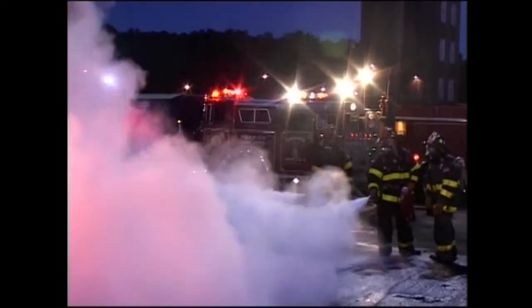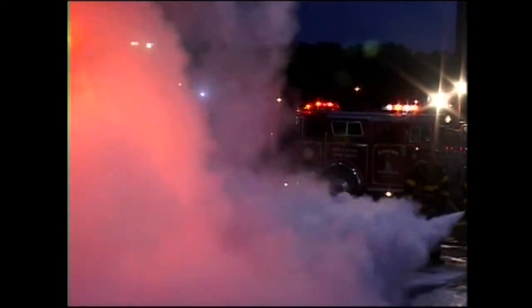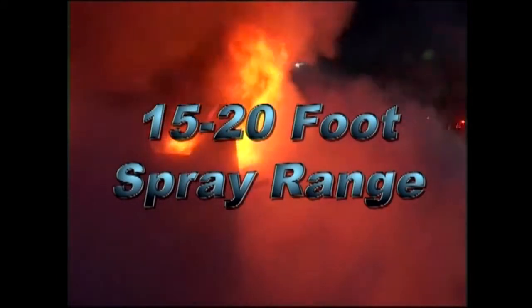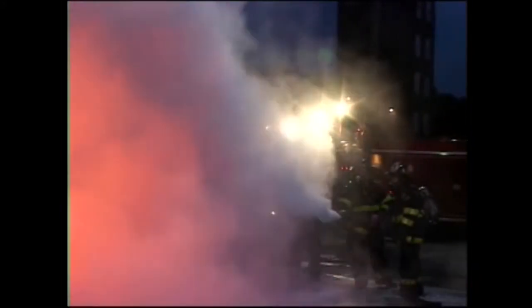From a safe distance, see if you can put the fire out using dry chemical extinguishers. Keep in mind, the chemical spray will only carry 15 to 20 feet, so you have to be aware of how close you get to the fire. Otherwise, you can become a victim.